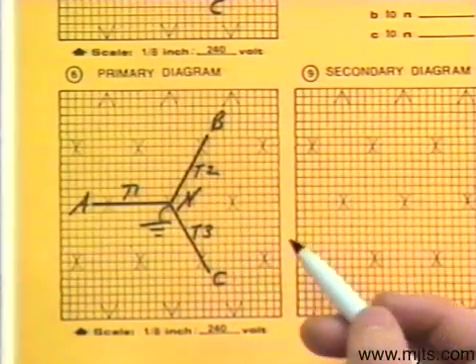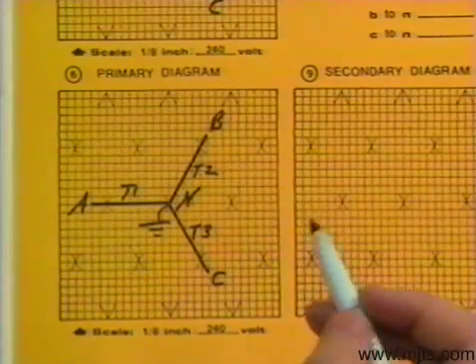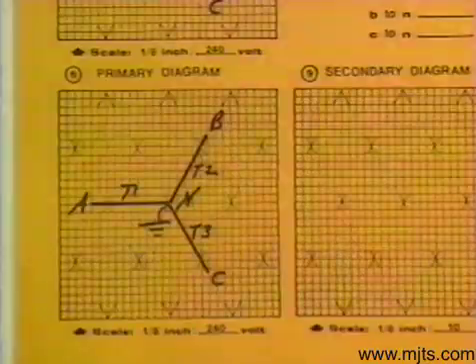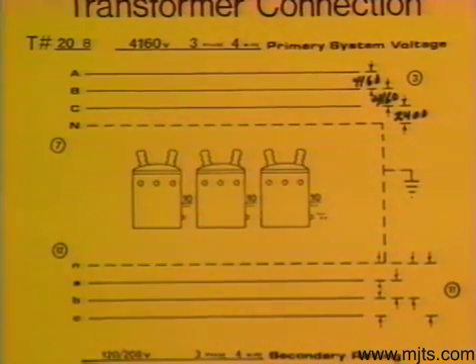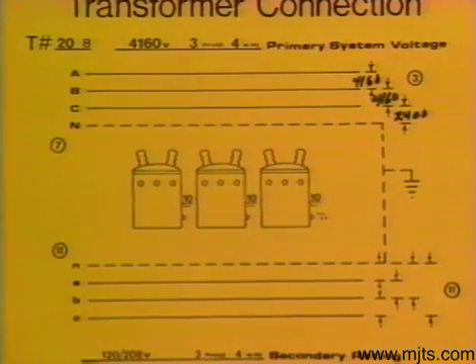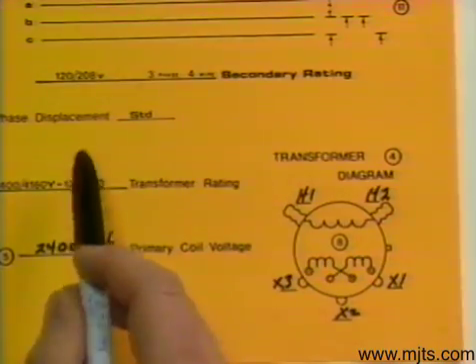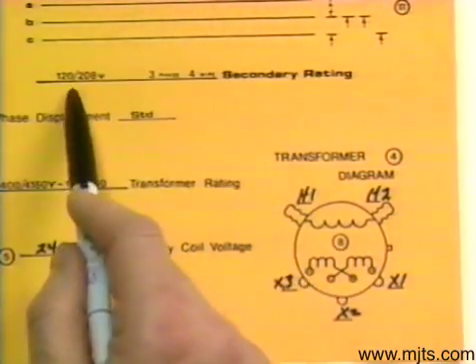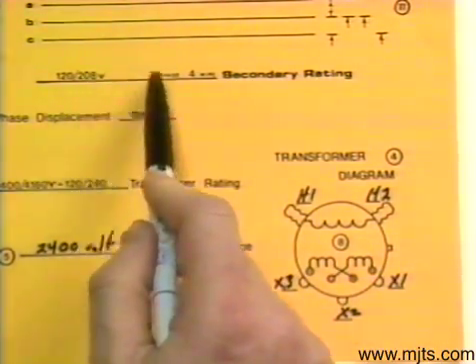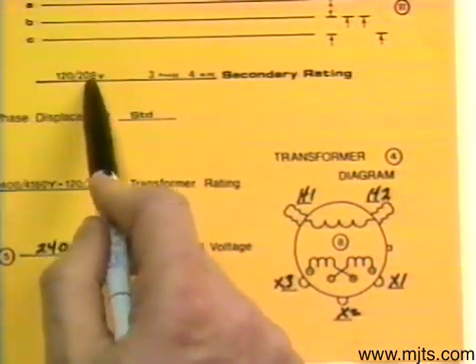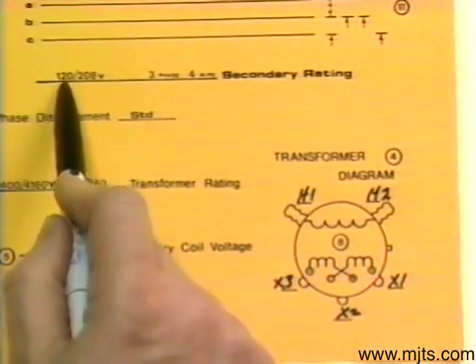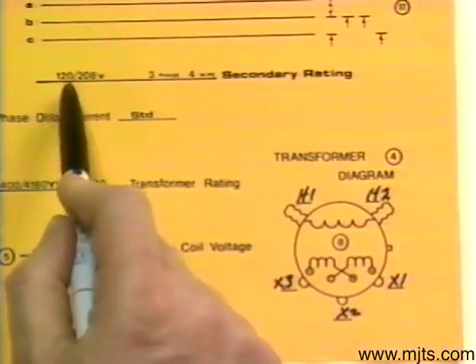Step seven will be left out until a later time — we'll skip it and go on to step eight. On the low side, the secondary rating we want is 120/208, 3-phase 4-wire. Those numbers tell us what kind of connection we need: 120 to 208 means we want a Y connection on the low side.